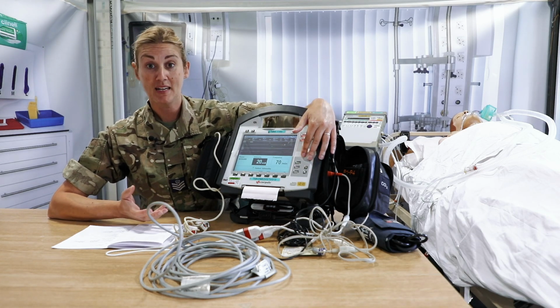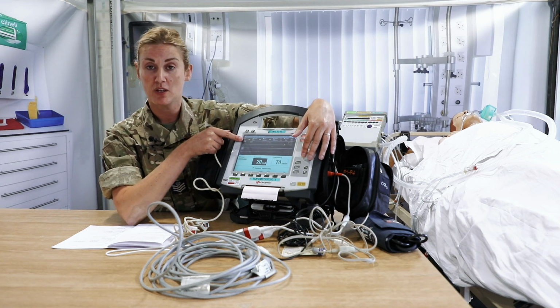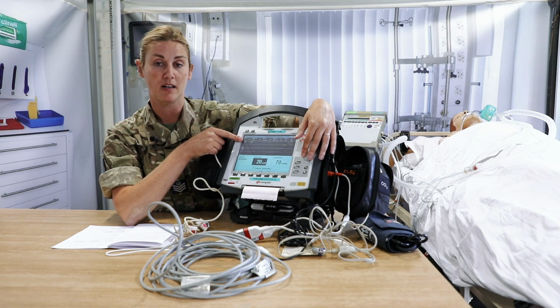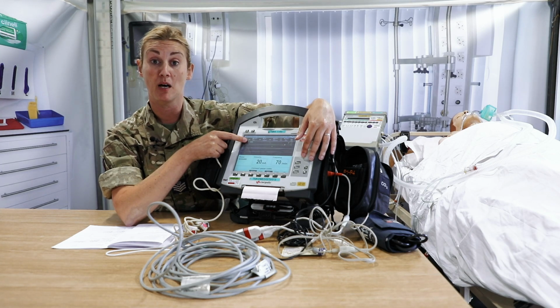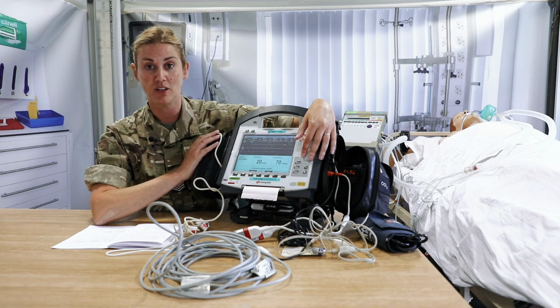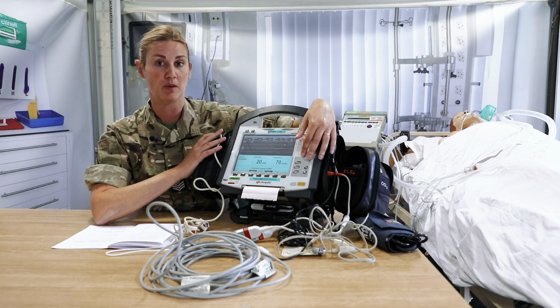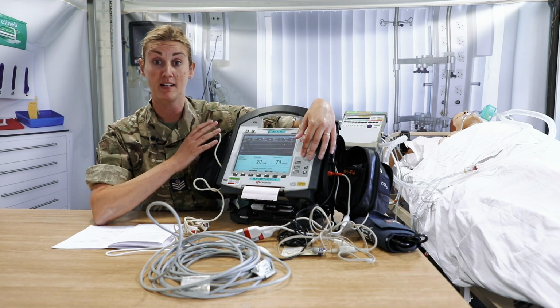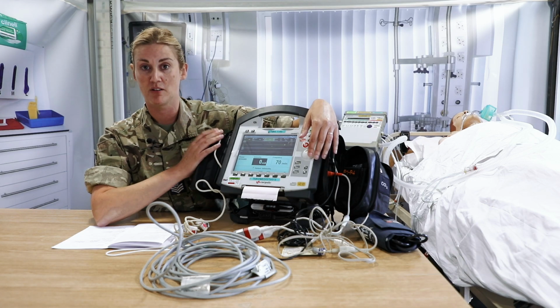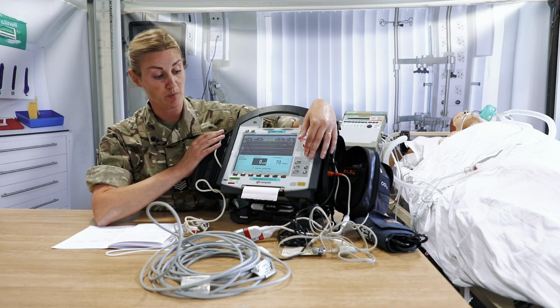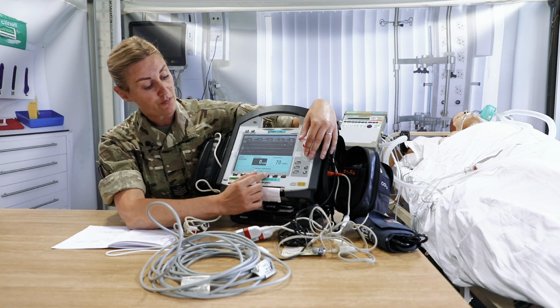It will make a loud noise, but you can see in the top screen with our ECG lead that this STIM has become available. And what that's telling you is that the Corpuls knows that the pacemaker is attached and ready to go, and it's looking for a stimulation to be able to pace. So in your intensity, just confirm that it goes up to 150 and then back down to 0, which effectively switches off the pacer. Next is the frequency button.